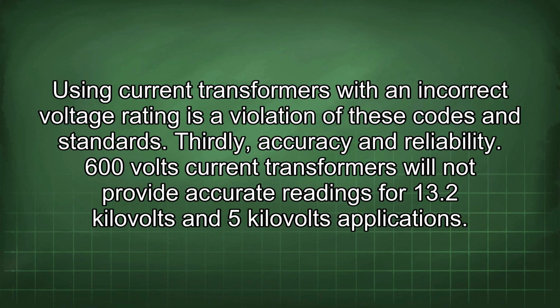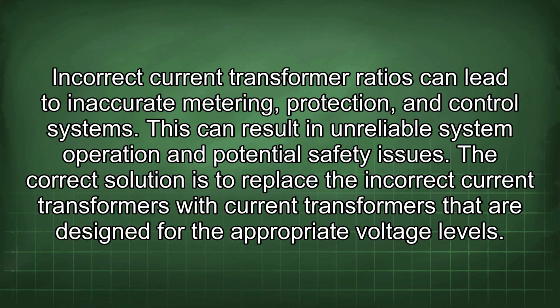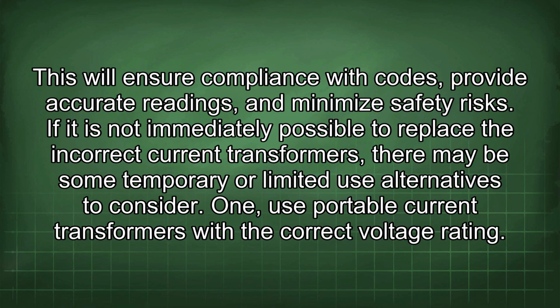Thirdly, accuracy and reliability. 600 volts current transformers will not provide accurate readings for 13.2 kV and 5 kV applications. Incorrect current transformer ratios can lead to inaccurate metering, protection, and control systems. This can result in unreliable system operation and potential safety issues. The correct solution is to replace the incorrect current transformers with current transformers that are designed for the appropriate voltage levels. This will ensure compliance with codes, provide accurate readings, and minimize safety risks.